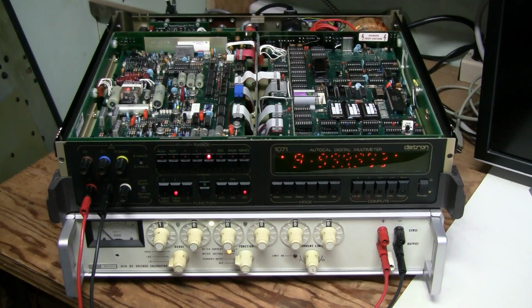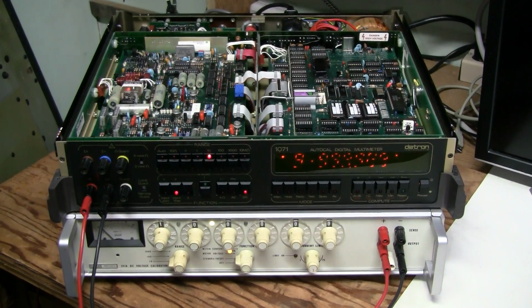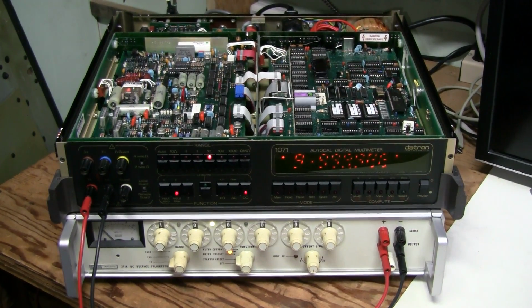So the fluke was in spec, but that really means within, let's say, 50 ppm or so, which is not really enough right now for calibrating this meter. So I think to proceed with calibration I need to trust my Hewlett-Packard meter instead of this fluke calibrator. The Hewlett-Packard meter is also more accurate according to specs than the fluke calibrator. Simply speaking, it is a 35 ppm unit. This is called basic DC accuracy in the manual.